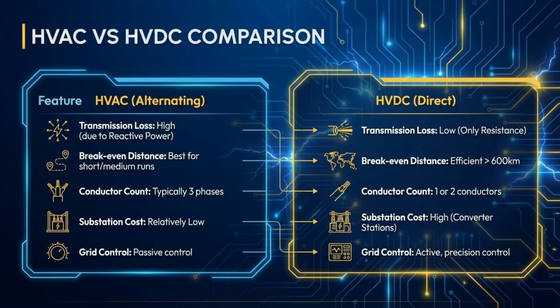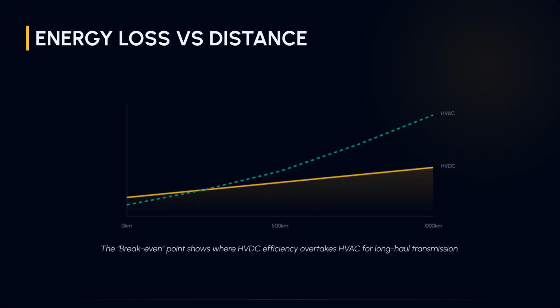Comparing HVAC and HVDC, AC is best for short runs with simpler substations. DC excels over long distances, offering lower losses and precise control, but requires costly converter stations. This chart illustrates energy loss versus distance. The break-even point is where the higher initial cost of HVDC is offset by its superior efficiency, making it the preferred choice for long-haul transmission.